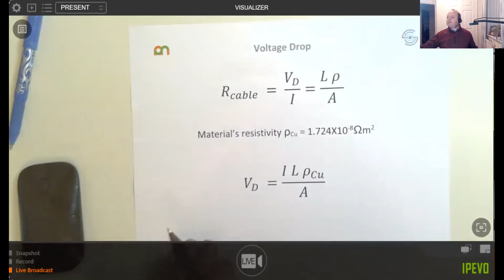So I thought we could have a little look at how you calculate that. It's a dead easy equation. We're looking at the resistance of the cable, since that's essentially what it is. Resistance is voltage divided by current, or as my grandfather said many years ago, very important rubbish. Resistance is also defined by the length times the material's resistivity divided by the cross-sectional area. That's all we need to work out what the voltage drop is.